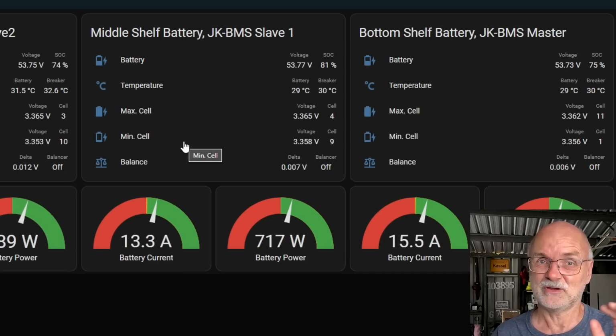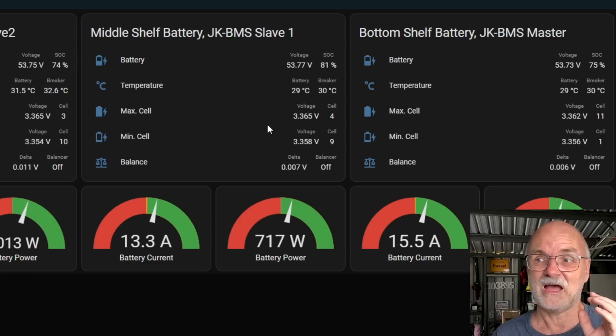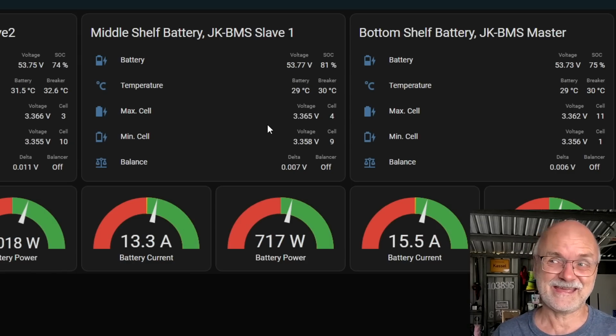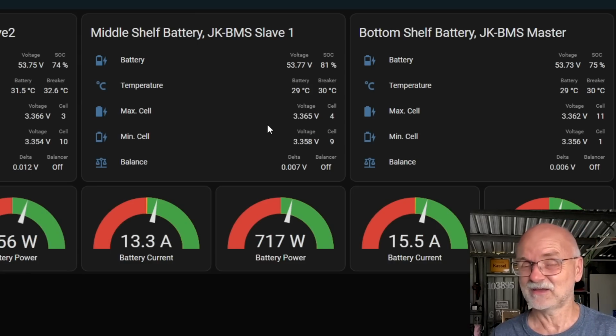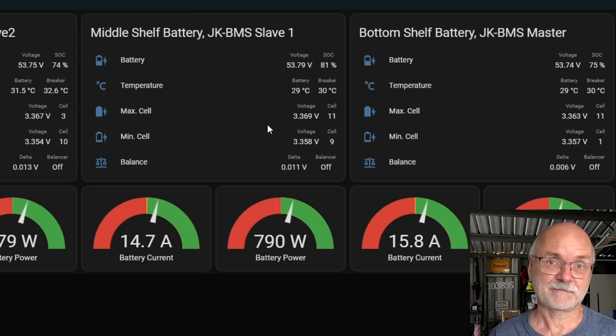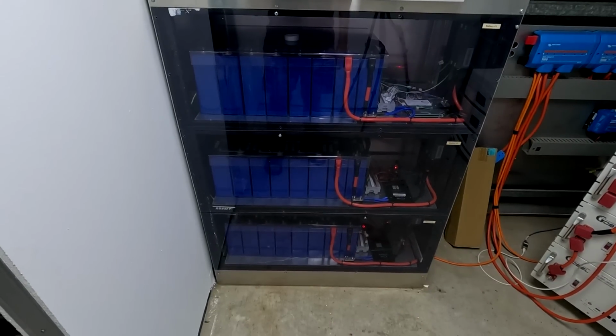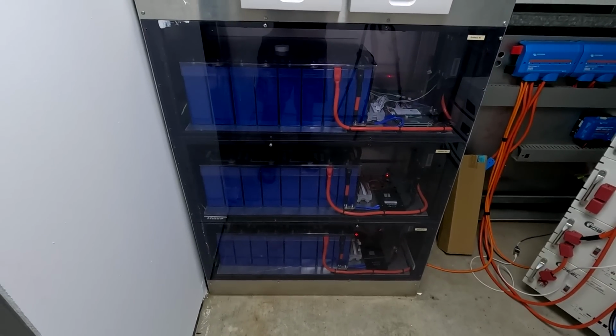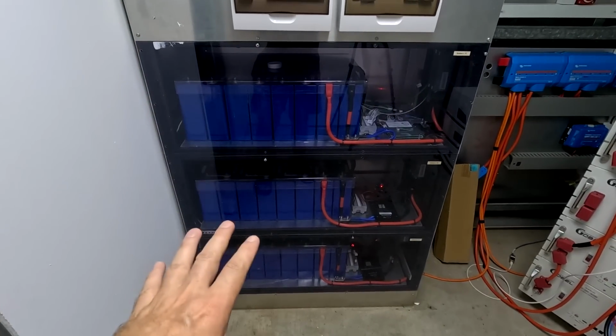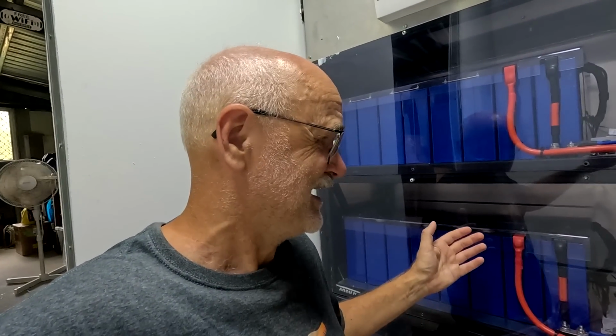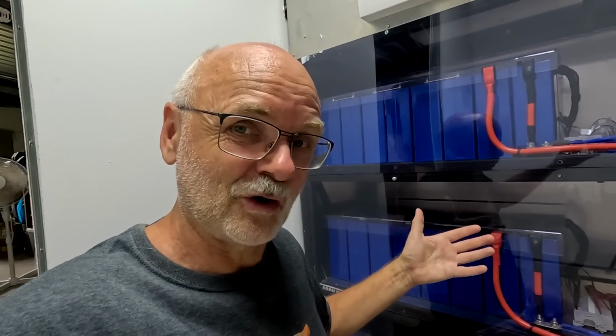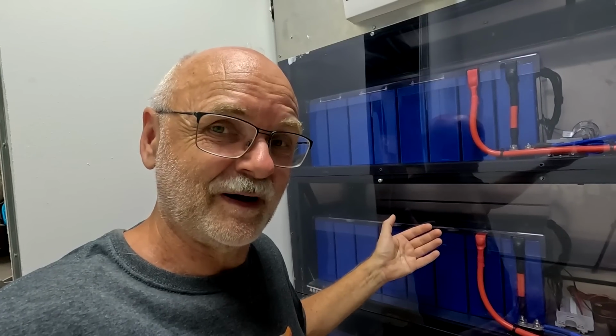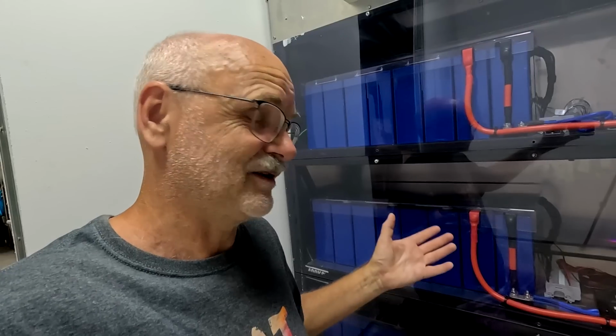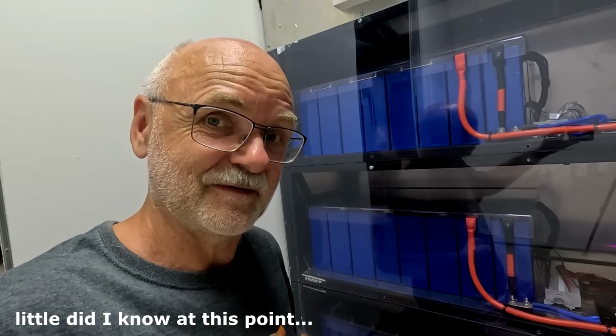But there's also a second problem with this middle shelf battery here, and it is also related, I think, to the aluminium bus bars. We had the aluminium bus bars installed pretty much since the beginning, so almost 3 years ago when we installed the battery shelf. This was also a bit of a long-term test to see if there's actually a difference long-term with these aluminium bus bars in comparison to copper bus bars. And it shows us here clearly it is.